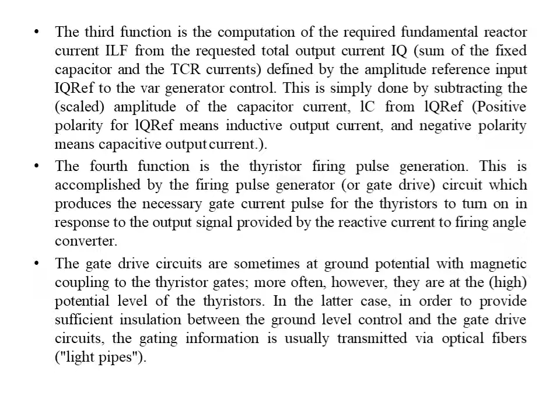The gate drive circuits are sometimes at ground potential with magnetic coupling to the thyristor gates. More often, however, they are at the high potential level of the thyristors. In the latter case, in order to provide sufficient insulation between ground level control and the gate drive circuit, the gating information is usually transmitted via optical fibers. So this gate drive circuit is grounded, and the next step is that we can directly transfer the gate signal using optical fibers, that is a light pipe.